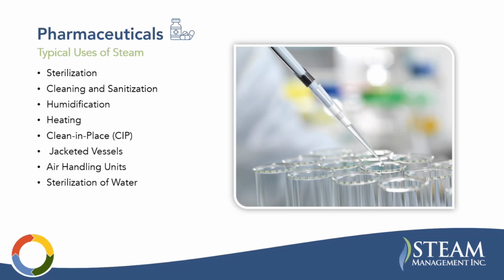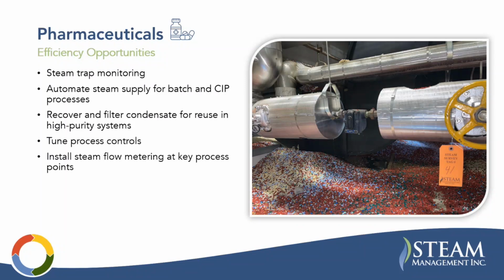There are steam jacketed vessels, all your air handling units and other HVAC requirements, and then water sterilization. Often in pharmaceuticals, you have water that's purified for injection into the product, and as you can imagine, there are stringent requirements there. Efficiency opportunities, steam trap monitoring again. I wouldn't say more than healthcare, but pharmaceuticals is also a particularly good opportunity for steam trap monitoring. These facilities usually have high run hours. They have high pressure lines. They have sprawling steam systems with a lot of traps, and again, maintenance crews that might be stretched thin, and critical processes that require properly functioning steam traps. So this is a really good application for steam trap monitoring.